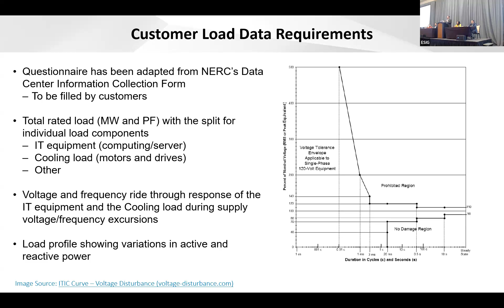I'll start with power quality. The first thing that comes to mind is harmonics. These are power factor corrected supplies with a lot of drives, meaning a lot of harmonic sources. So these facilities implement harmonic mitigation measures, like filter banks, so that the net harmonic injection into the utility system is limited.